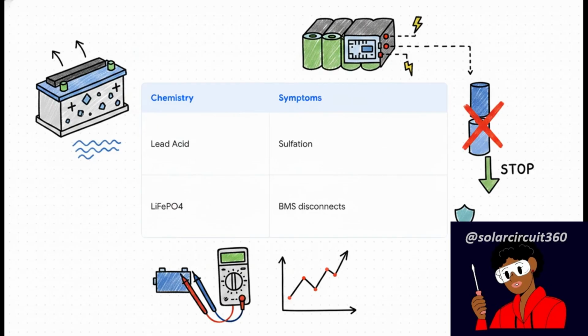Now, keep in mind, you really need to know your specific battery chemistry, because the symptoms change. For lead acid, internal resistance usually spikes because of sulfation, stratification, or literal physical damage to the plates. But if you're rocking a lithium setup, like LiFePO4, you're usually looking at cell imbalance, damaged parallel groups, or, very commonly, BMS disconnects. Your lithium battery's management system might suddenly cut the power to protect itself from a low-voltage cell event, and that perfectly mimics a dead battery. So don't automatically assume a sudden shutdown means a totally dead battery. It could just be the BMS stepping in to save the day for an imbalanced cell.